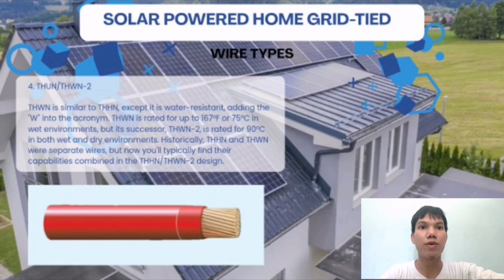The W stands for water resistant, signifying that this wire isn't just moisture resistant, it's physically engineered to handle being submerged or exposed to heavy water flow without the insulation losing its electrical integrity. Electricians used to choose between THHN for heat or THWN for wet environments, but modern engineering has merged them. THWN2 is the current gold standard because it's rated for 90 degrees Celsius in both wet and dry conditions.